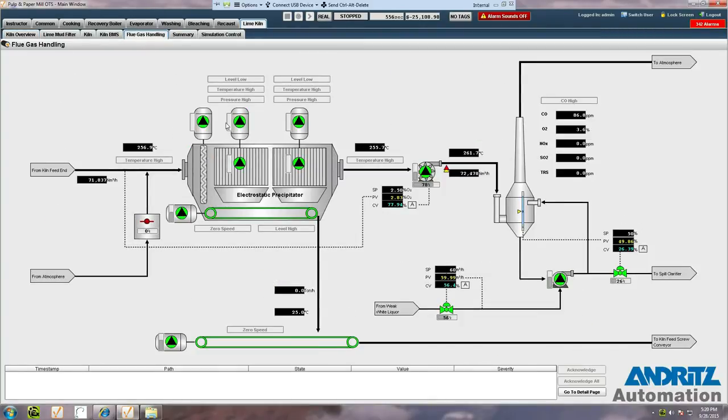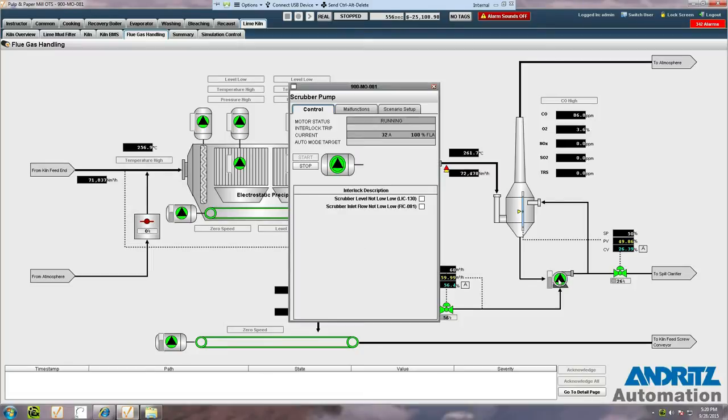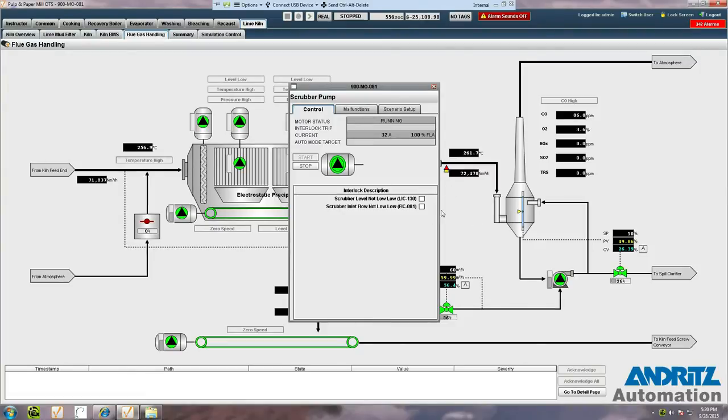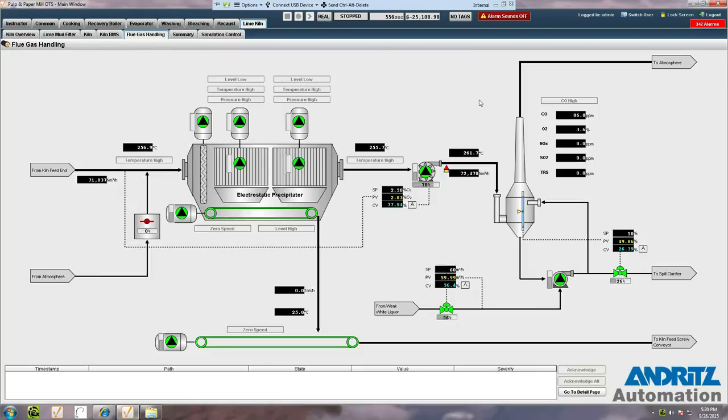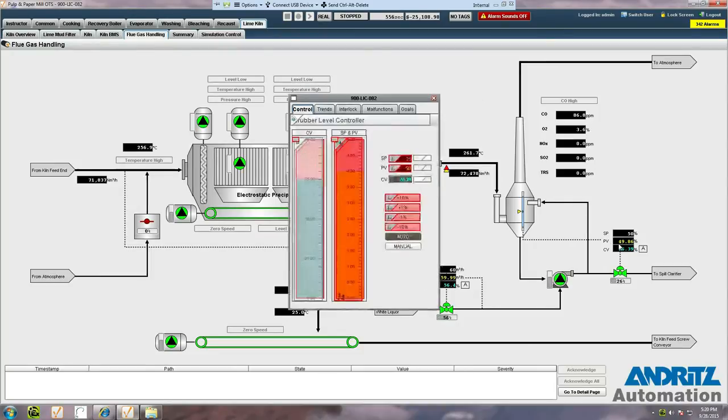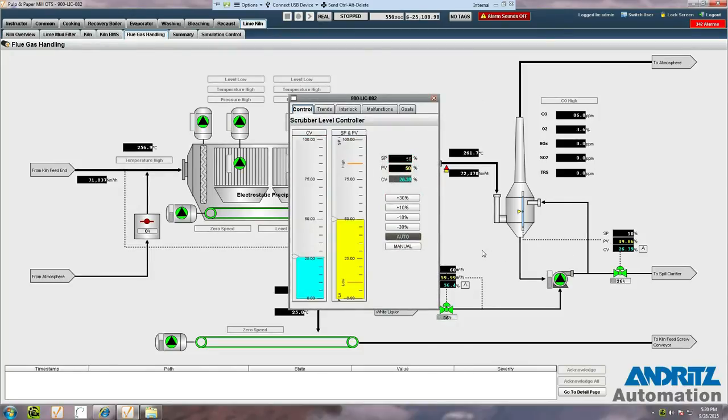Each area has multiple detail pages which allow access to the individual equipment pop-ups. Motors, as you can see here, provide a complete interlock list and first out indication would appear here if the motor had been recently tripped. Similarly, PID loops show the same set of features as a normal DCS interface.